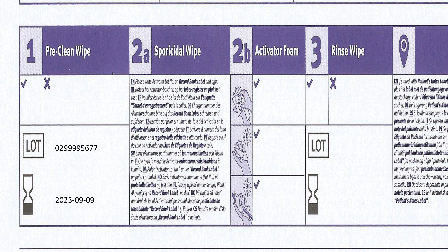In this section of the record book, we will find the area to document the decontamination process. Data of the pre-clean wipe, which is orange in color, will be recorded. It will include the lot number and the expiry date. For the sporicidal wipe, we will put a sticker. This sticker contains the lot number of the wipe and the expiry date of the wipe. And for the third rinse wipe, which is green in color, we will write the lot number of this wipe and the expiry date. So in this item, we must record 6 items: lot number and expiry date for wipe number 1, wipe number 2, and wipe number 3.